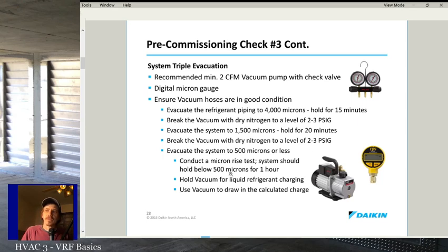The ideal is, after you get it down below 500 microns, to hold somewhere below 500 microns for an hour. That doesn't mean go down to 220 microns and watch it slowly rise to 500 and it takes an hour to get to 500. That means you should hold pretty damn steady at some point below 500. If you can hold that for an hour, that system's good.